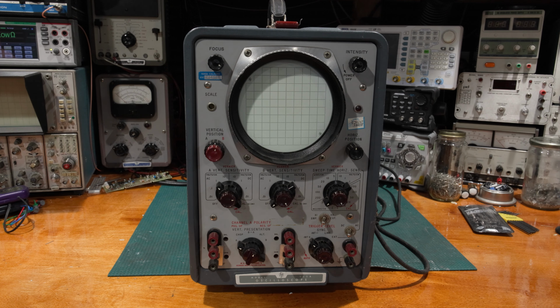However, pretty much everything in the focus and intensity section got damaged, other than the grid control, because there's no current in the grid control, it's just voltage bias. But that voltage divider string, everything has to be rebuilt.